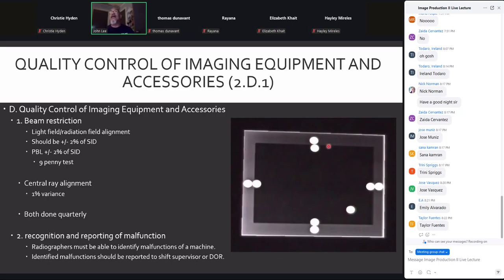Here it's dead on. The radiation field, if it's congruent, should fall right between the two pennies. Here it's a little off. Here it's a little more off than it is here. And here is about the same as here. So this one is the only collimator leaf that is dead on with the radiation field and the light field. Now, are these within that 2%? Yes. If the radiation field extended beyond the diameter of either one of these pennies, then we're outside of the 2% margin of error, and we would have to call someone in to make an adjustment to that unit. That's why we use pennies.